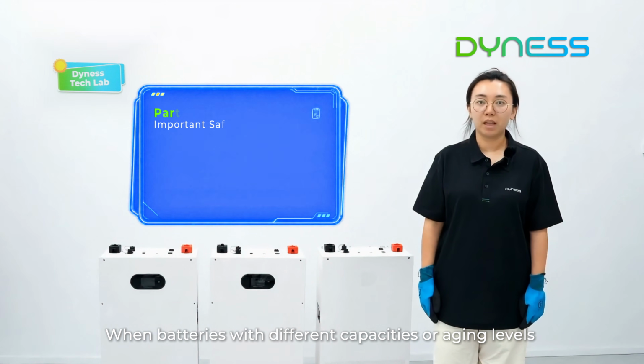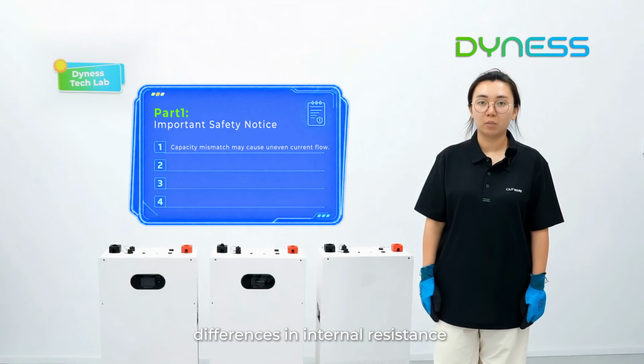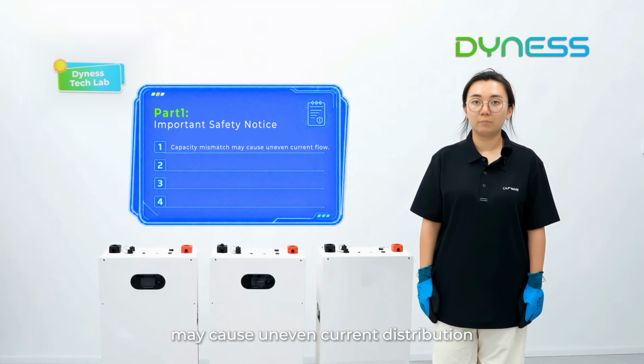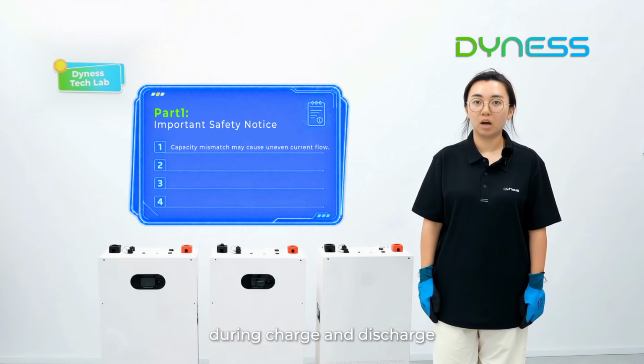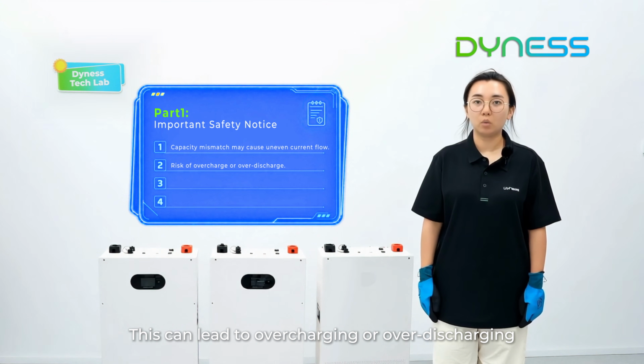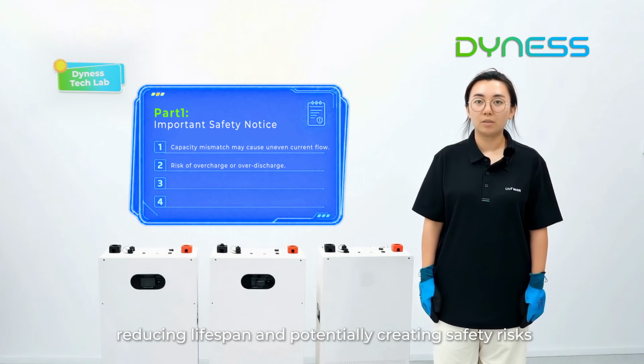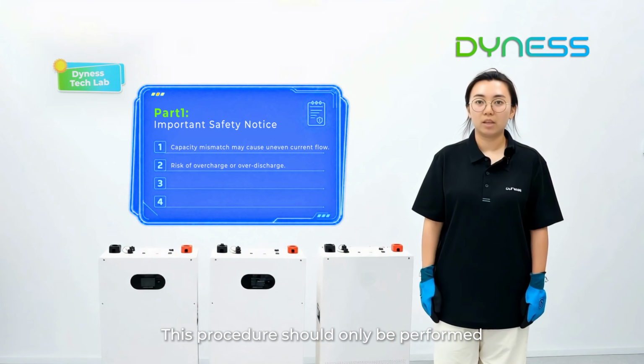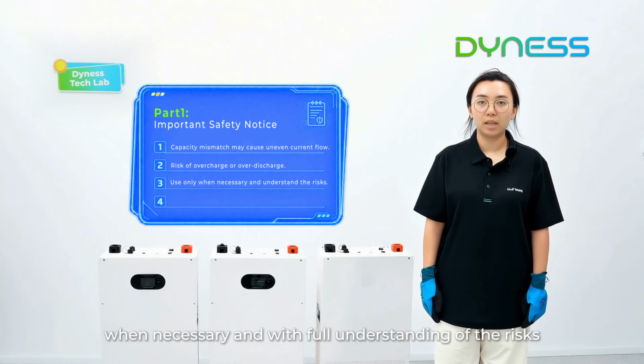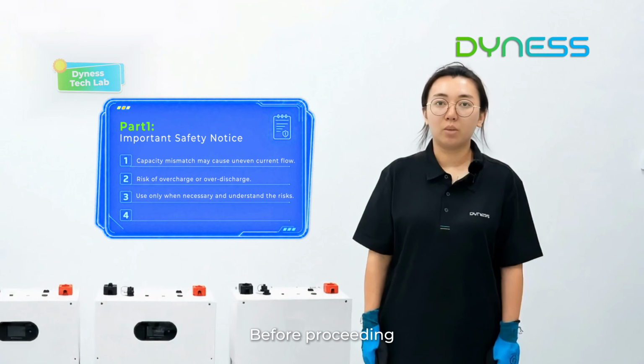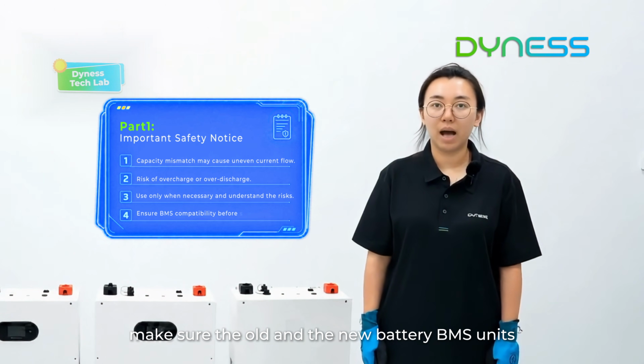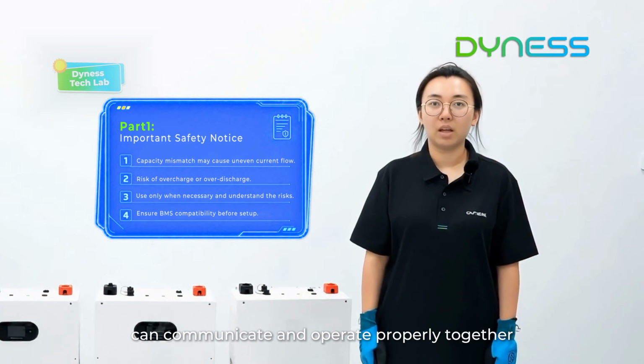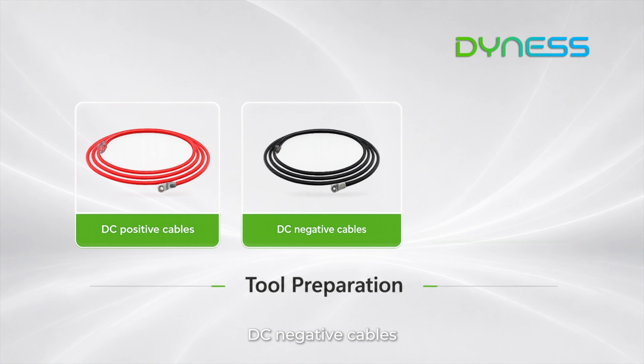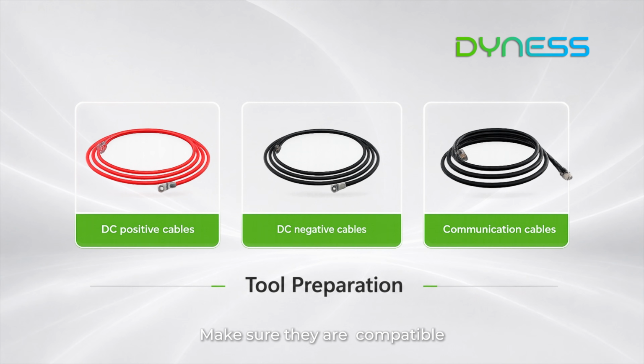When batteries with different capacities or aging levels are connected in parallel, differences in internal resistance may cause uneven current distribution during charge and discharge. This can lead to overcharging or overdischarging of certain batteries, reducing lifespan and potentially creating safety risks. This procedure should only be performed when necessary and with full understanding of the risks. Before proceeding, make sure the old and the new battery BMS units can communicate and operate properly together. Tools: prepare the following: DC positive cables, DC negative cables, communication cables. Make sure they are compatible with the battery and inverter interfaces.